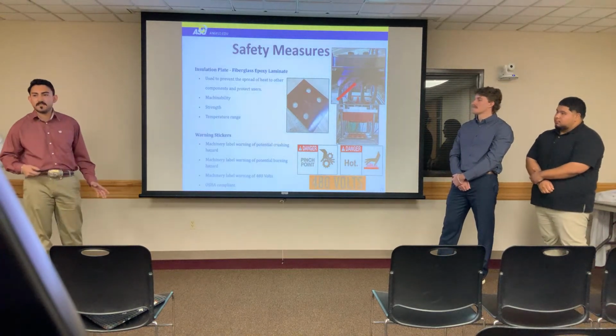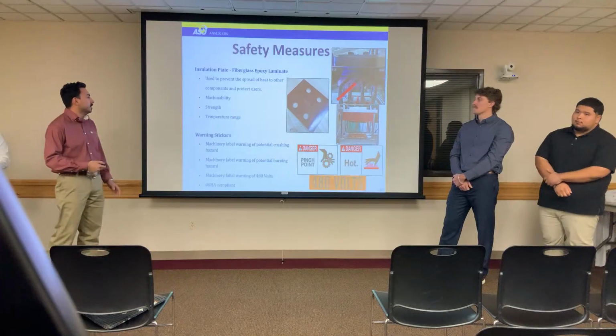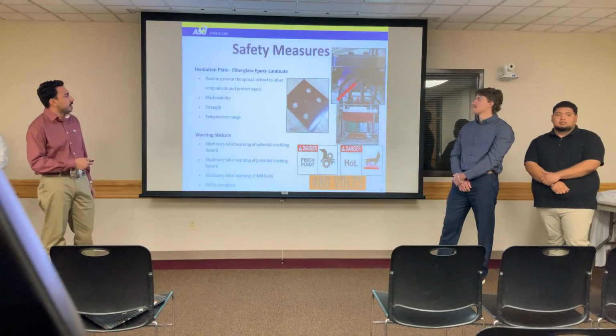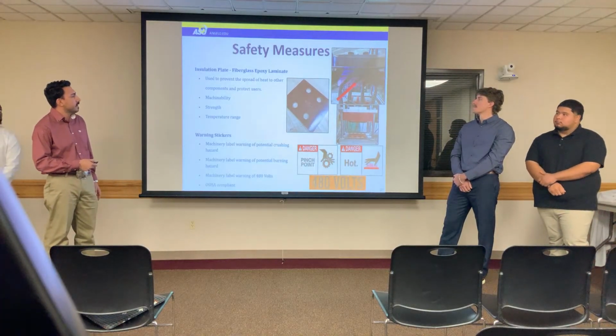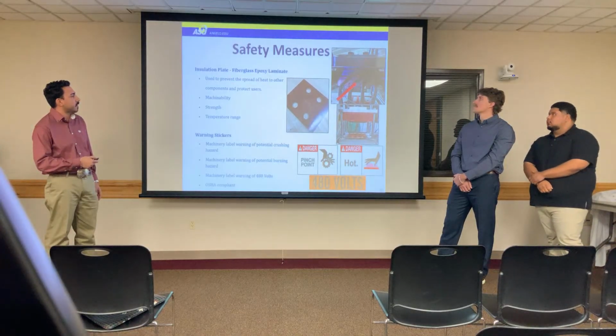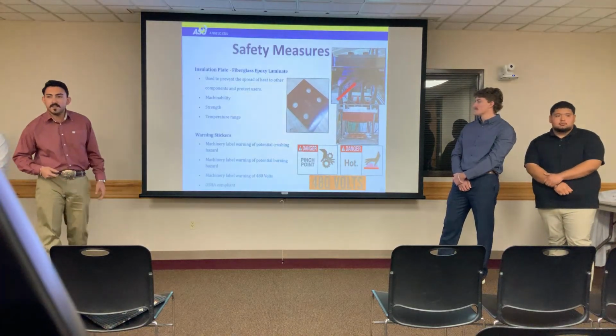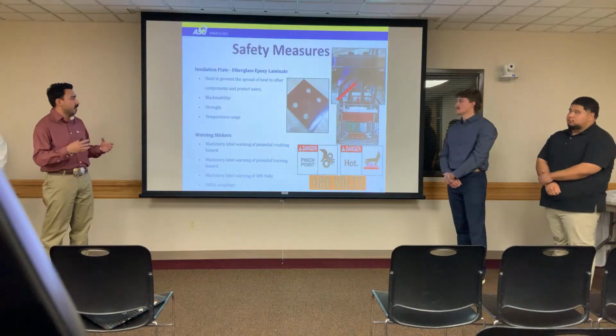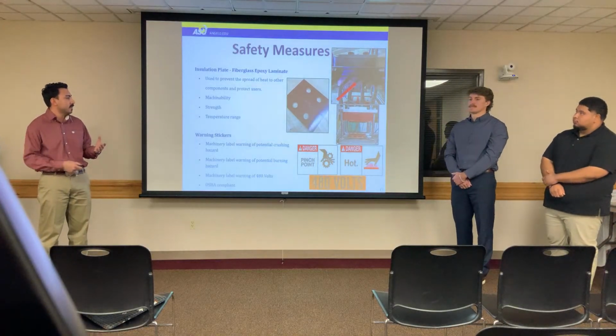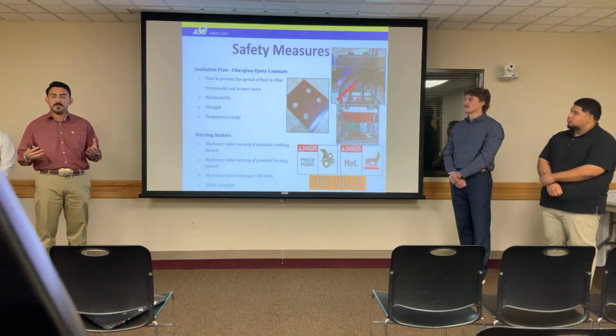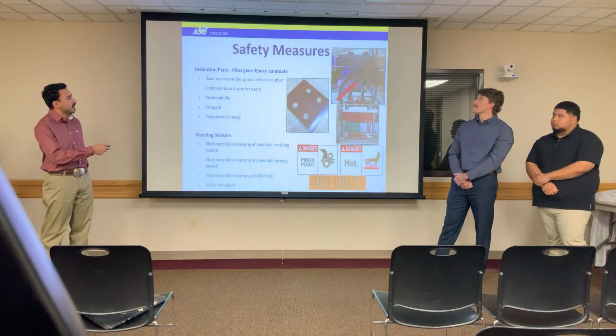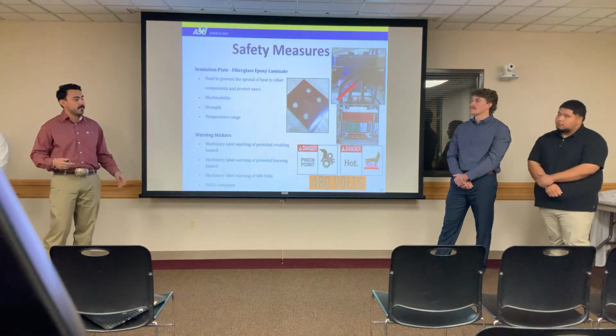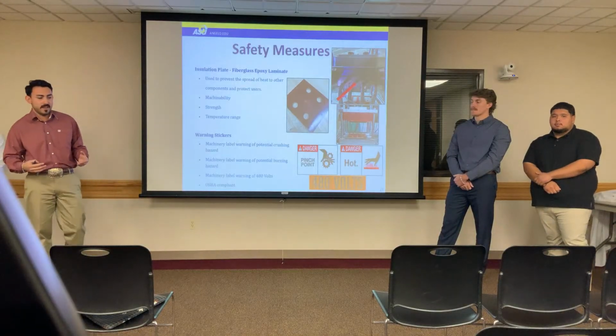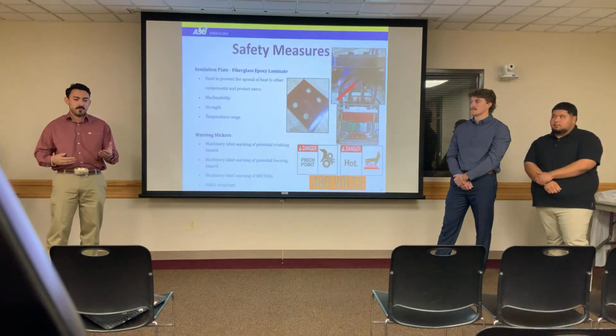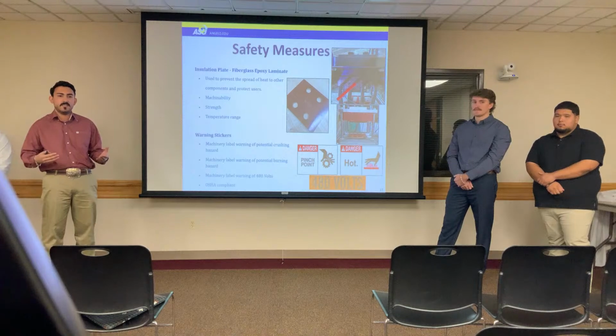In addition to those safety measures, we had an insulation plate, a fiberglass epoxy laminate, located between our top die, our load cell transfer plate, and our top plate. This insulates the whole machine and also protects the user, but insulation is the main priority since our load cell is located up there. We don't want it to get too hot, because it reads through resistance - when you increase heat, you increase resistance.